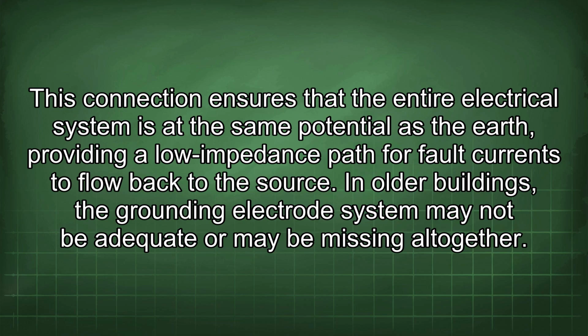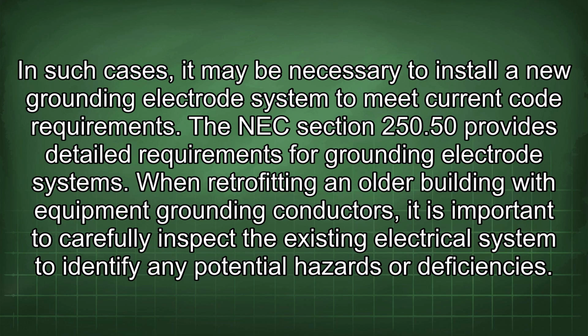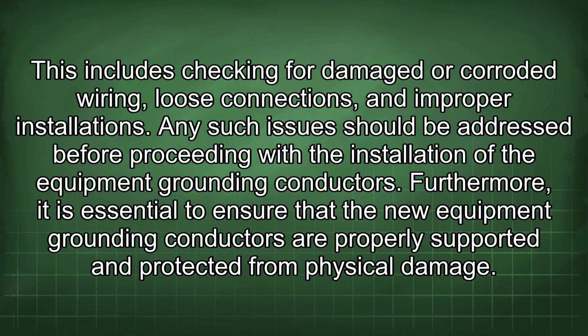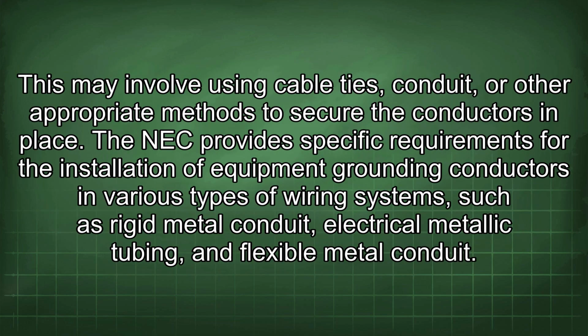In older buildings, the grounding electrode system may not be adequate or may be missing altogether. In such cases, it may be necessary to install a new grounding electrode system to meet current code requirements. The NEC section 250.50 provides detailed requirements for grounding electrode systems. When retrofitting an older building with equipment grounding conductors, it is important to carefully inspect the existing electrical system to identify any potential hazards or deficiencies. This includes checking for damaged or corroded wiring, loose connections, and improper installations. Any such issues should be addressed before proceeding with the installation of the equipment grounding conductors. Furthermore, it is essential to ensure that the new equipment grounding conductors are properly supported and protected from physical damage. This may involve using cable ties, conduit, or other appropriate methods to secure the conductors in place.